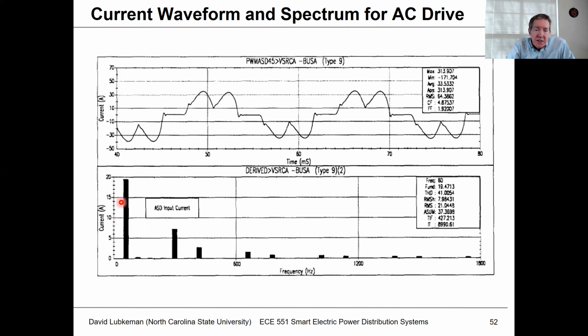Now, what you'll again see here is when you have a three-phase device and you're doing rectification, you don't get the third harmonics. What you would get is the fifth and the seventh harmonics. So usually the pattern is you get the fifth, the seventh, the 11th, the 13th. Then usually after that, we're not as concerned anymore.